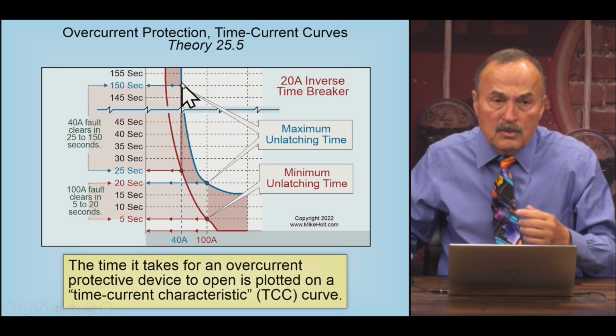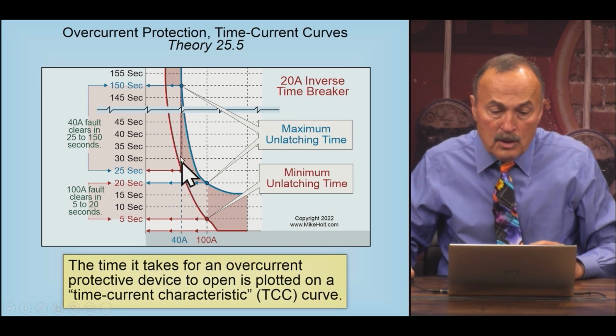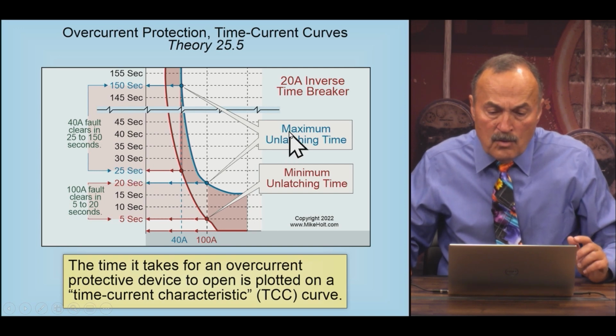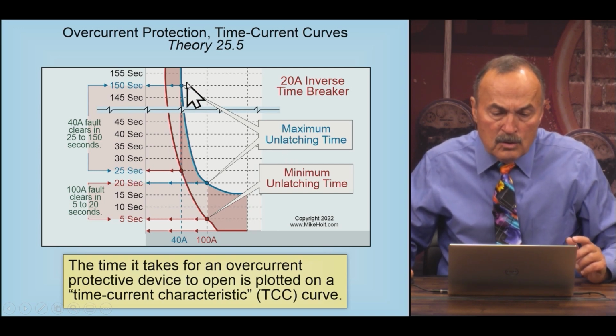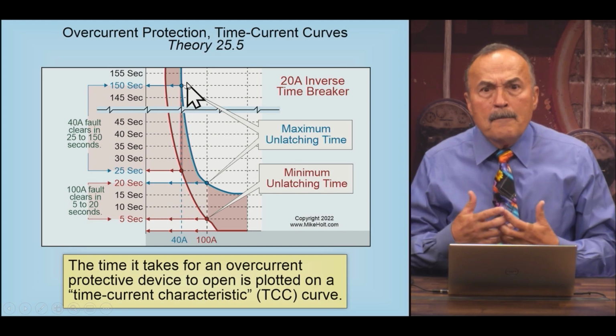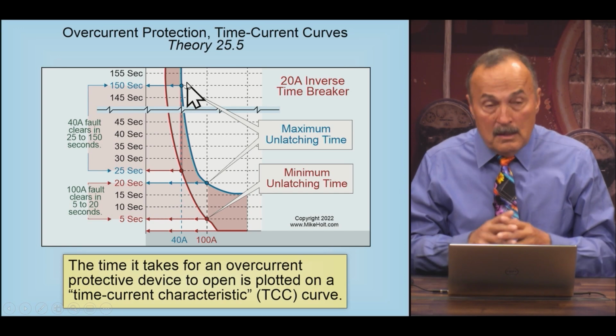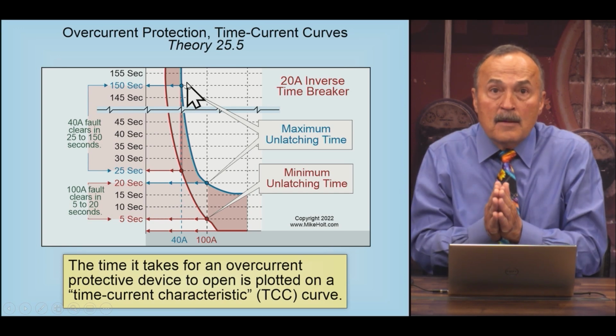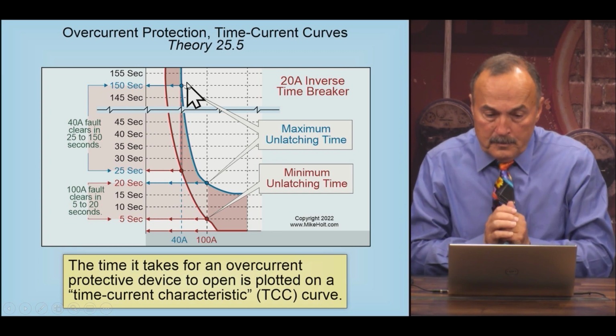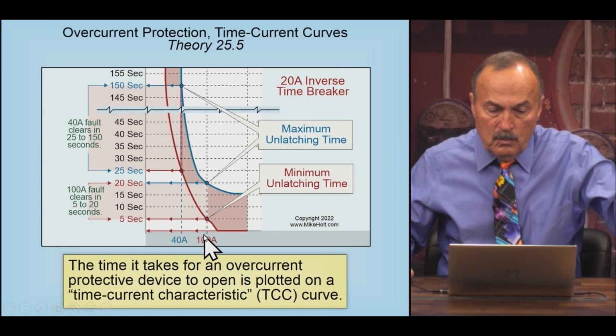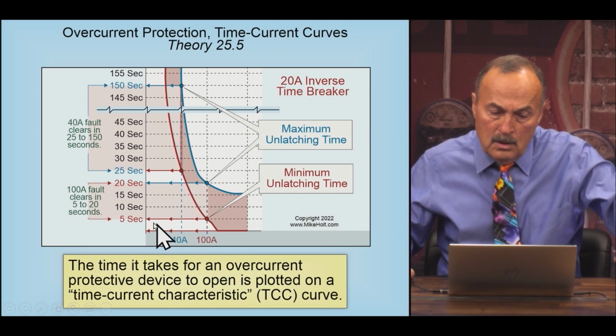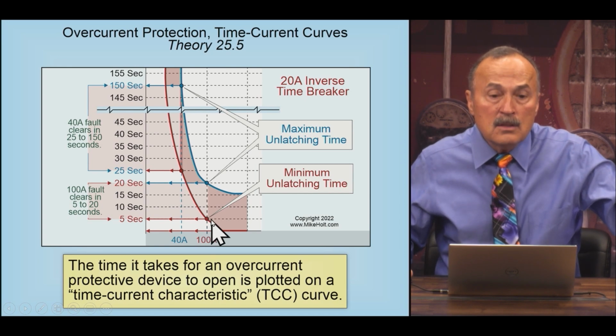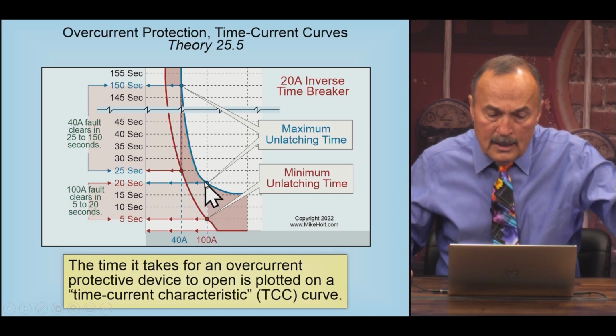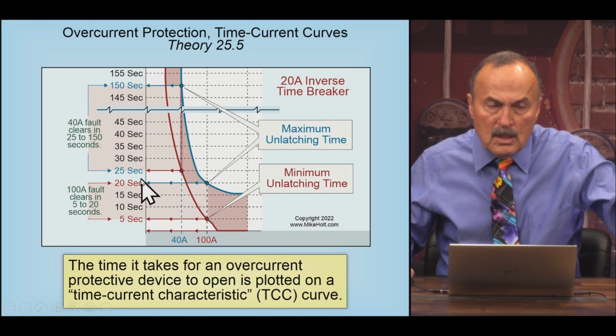Yeah. So assuming it's installed at the ambient temperature it's calculated at, and assuming we have the time current characteristic curves, we can say a 40 amp load on a 20 amp breaker has a minimum tripping time of about 25 seconds. The maximum unlatching time would be about 2.5 minutes, and that's what it looks like. So that's why 40 amps on a 20 amp breaker is not going to trip instantaneously: it's heat, it's a bimetal bending. Now, let's go with 100 amps. If you had 100 amps, you go up and over, minimum maybe 5 seconds, and the unlatching time is between 5 seconds and maybe up to 20 seconds.